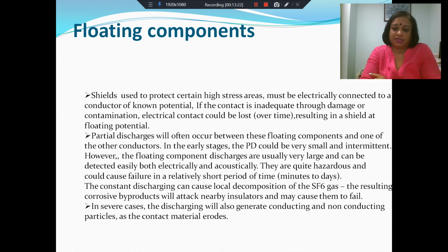Another problem is that even if it doesn't cause failure, if you have continuous discharges happening between the floating shields and the conductors, there would be continuous decomposition of the SF6 gas. And the resultant byproducts might be corrosive, and they might chemically attack the components and the materials around it, and may drive that insulation to failure through a secondary mechanism.